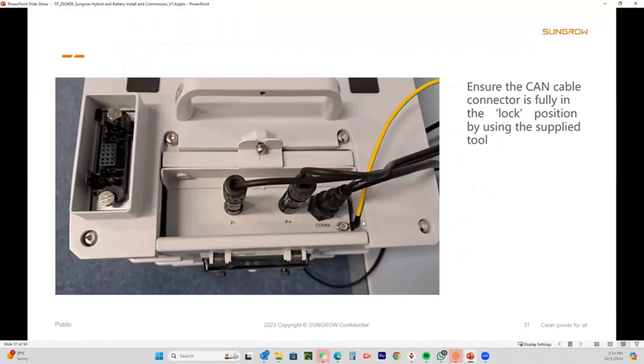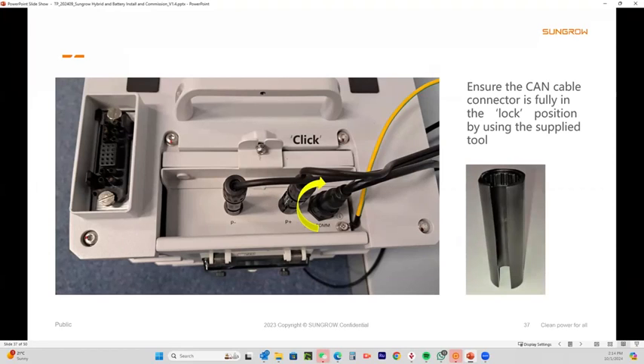Now, the communication cable has a locking ring here. It must actually lock, for 2 reasons. One is for the IP rating, which is IP55, and the other is to make sure there's a proper connection. If you do it by hand it will feel really tight and you think it's in place, but it's not. It has to click into position, so we provide this little tool. It slots over the cable, you turn it, and you'll feel it clunk into place and you know it's locked. If you don't lock it, it will work loose and you'll get a communication error with the battery.